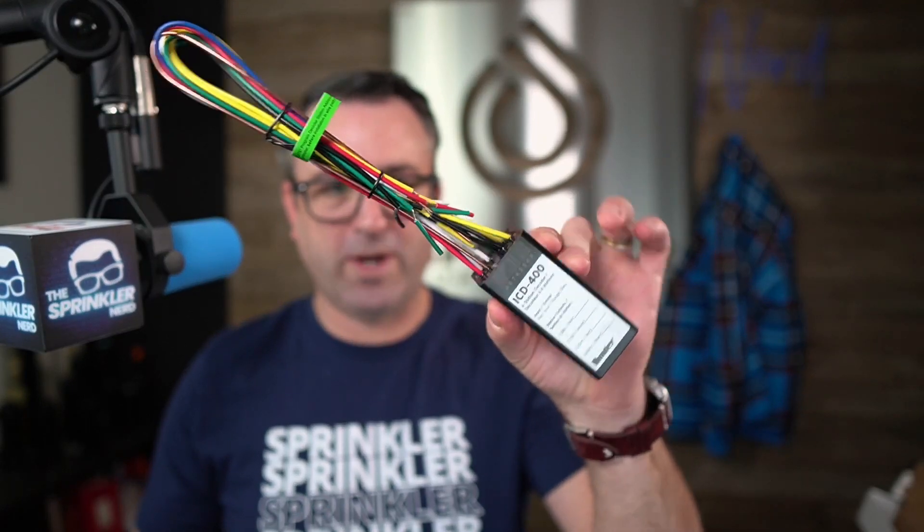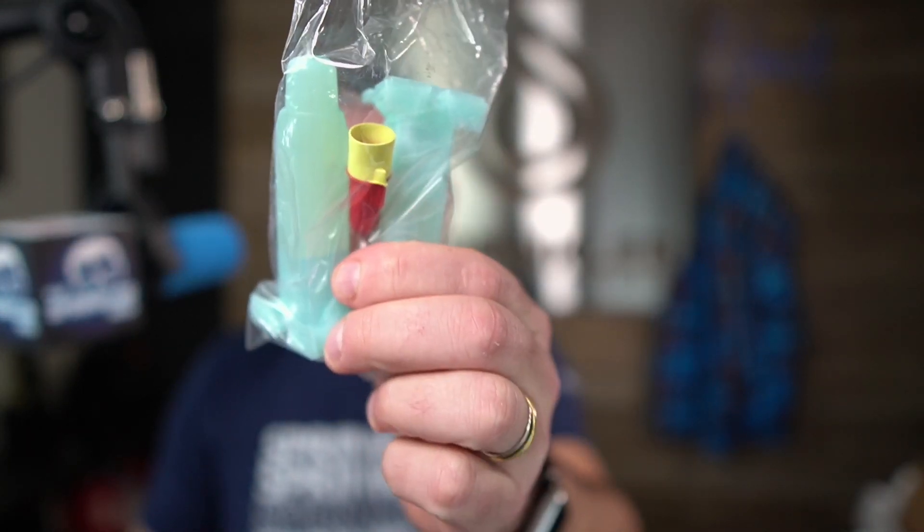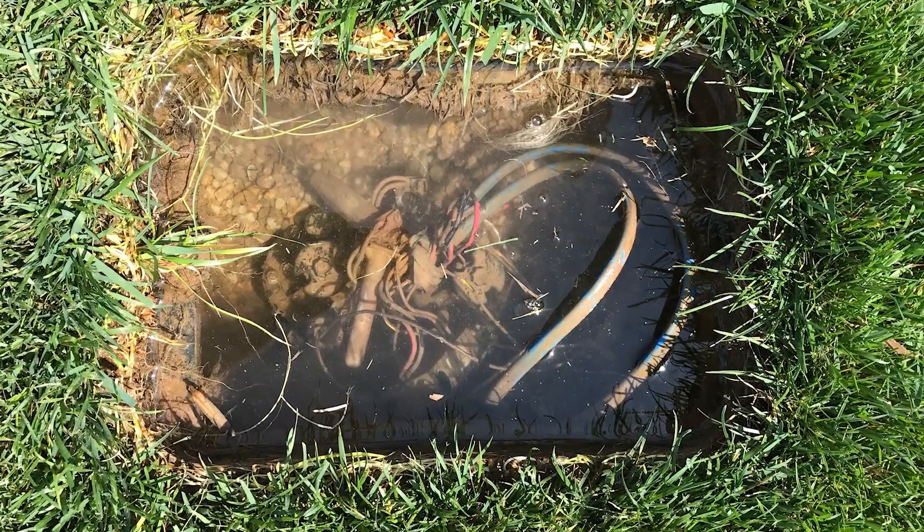Keep in mind every zone should be unique — you don't want to have two or three or four decoders all programmed to zone fifty. You want every zone to be unique. As a final statement: on two-wire systems, making a good splice connection is key. The main failure of any two-wire system is the wire connection, so please only use DryConn connectors such as this. The decoder itself is fully submersible, so if your valve box fills up with water, that's okay. But if you don't use the right splice kit, water can get into the splice and that's when failures occur.